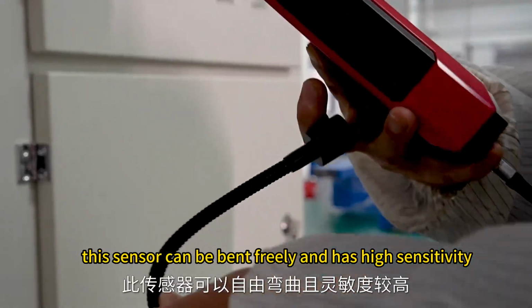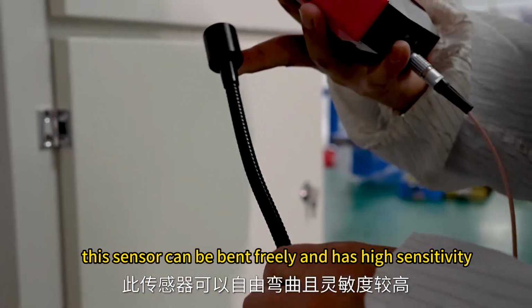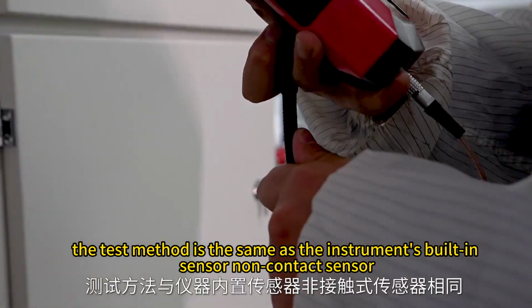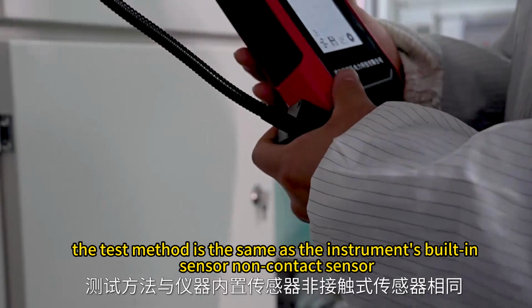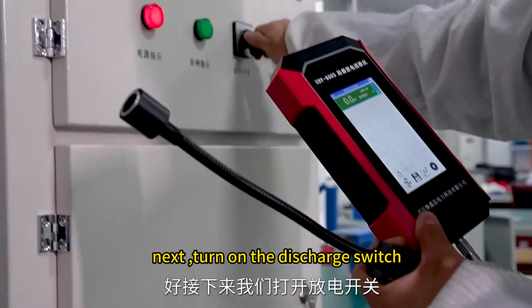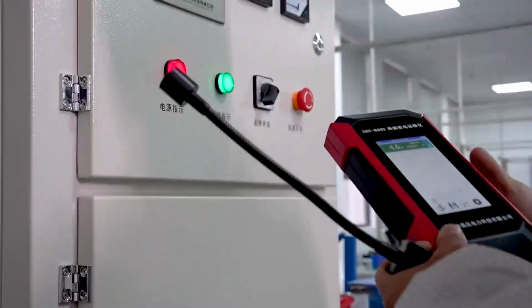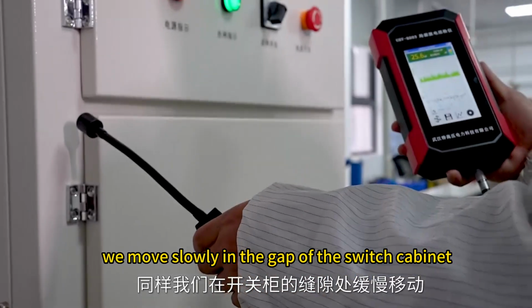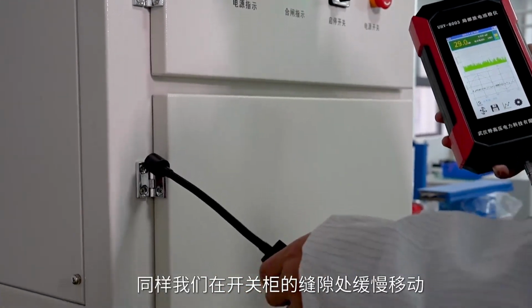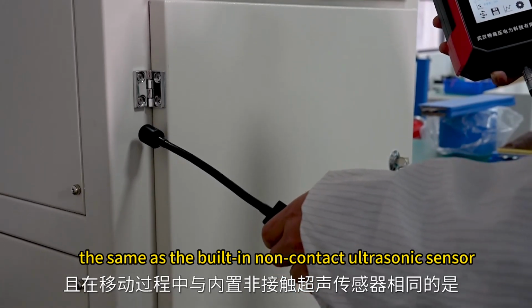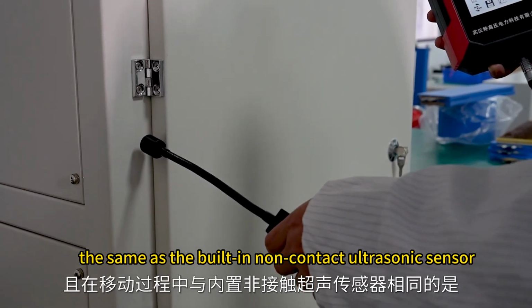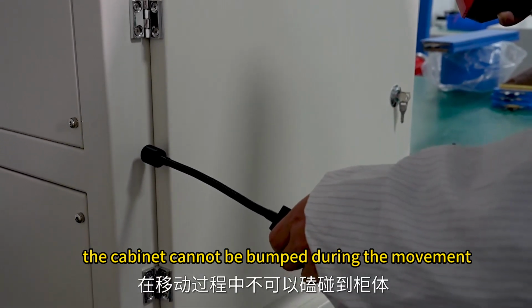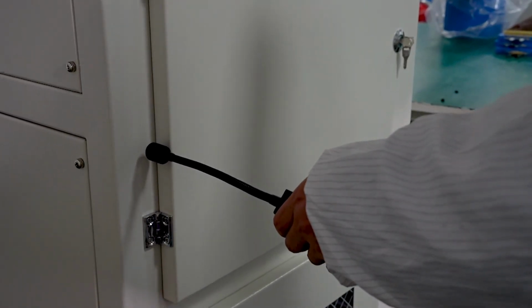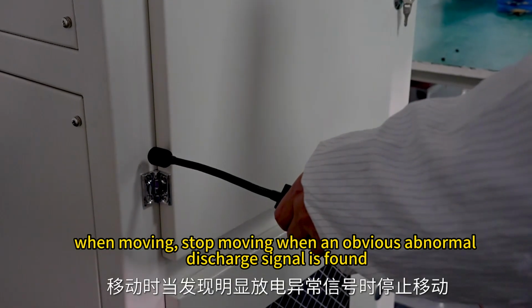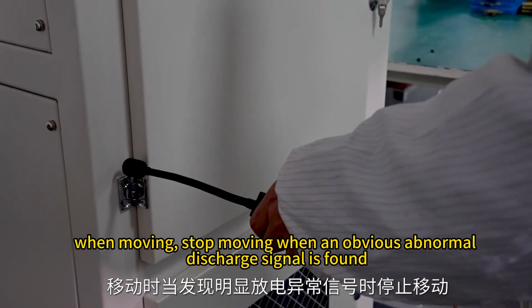This sensor can be bent freely and has high sensitivity. The test method is the same as the instrument's built-in, non-contact sensor. Next, turn on the discharge switch. Similarly, we move slowly in the gap of the switch cabinet. And in the process of moving, the same as the built-in non-contact ultrasonic sensor, the cabinet cannot be bumped during the movement. When moving, stop moving when an obvious abnormal discharge signal is found.